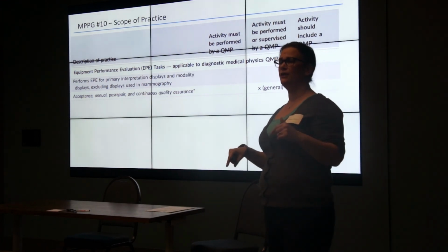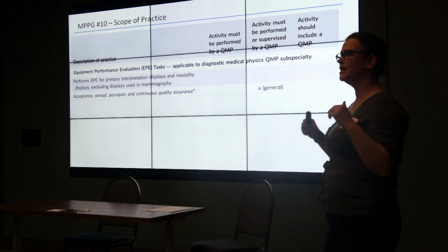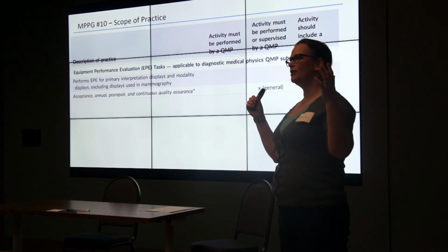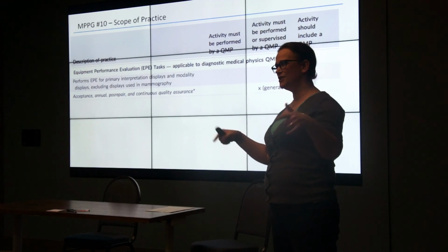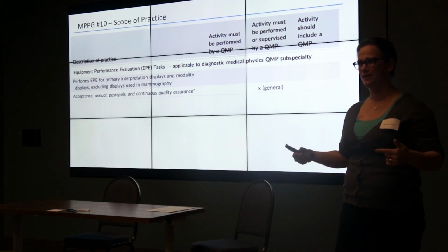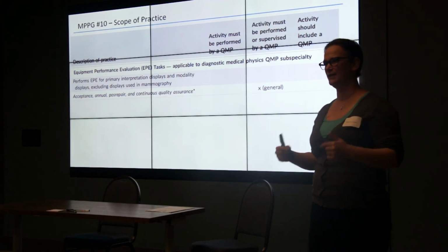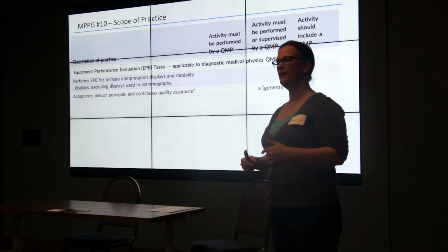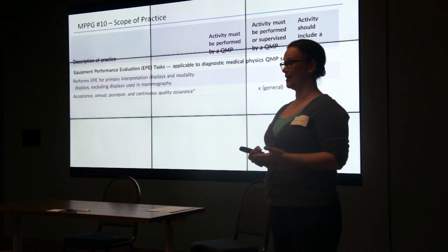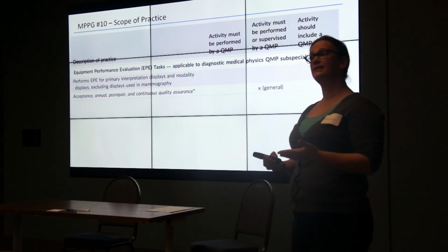And this is particularly relevant because in the state of Colorado, there are revisions underway for some of the Colorado regulations. One of the things that's in there is that every single diagnostic display has to be tested on an annual basis by a QMP. And I read that and I'm like, I don't want to do that. And I don't think it's necessary.